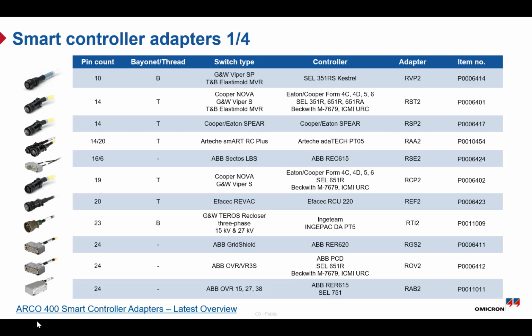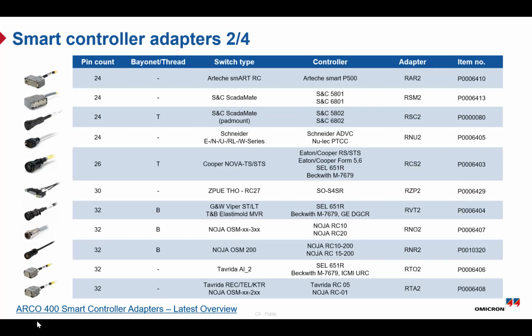There are also additional accessories for voltage connections depending on how the signals are provided by the recloser. So overall, these smart adapters make the connection process fast, flexible, and suitable for a wide range of applications. So with Omicron Smart Connect technology, the setup is truly plug and play. The system automatically recognizes the connected adapter, so there is no need for manual configuration.